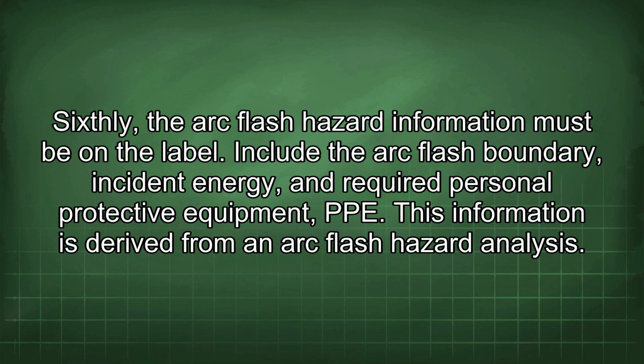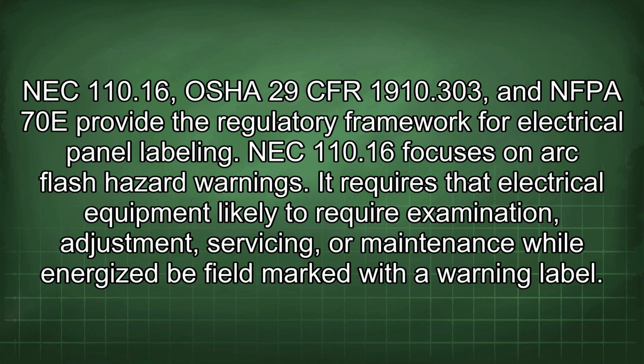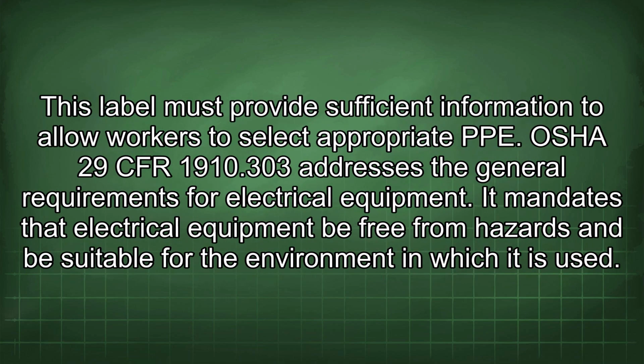Sixthly, the arc flash hazard information must be on the label. Include the arc flash boundary, incident energy, and required personal protective equipment (PPE). This information is derived from an arc flash hazard analysis. NEC 110.16, OSHA 29 CFR 1910.303, and NFPA 70E provide the regulatory framework for electrical panel labeling. NEC 110.16 focuses on arc flash hazard warnings. It requires that electrical equipment likely to require examination, adjustment, servicing, or maintenance while energized be field marked with a warning label. This label must provide sufficient information to allow workers to select appropriate PPE.